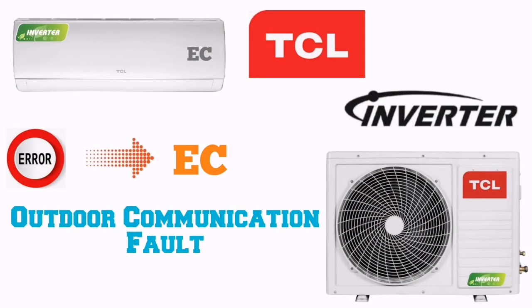When you see error EC on your display, it means outdoor communication fault. To solve this issue, the first point is to check the contact of communication wire C and 5 between the power source board and the intelligent power module. Insert it again if it is loose.